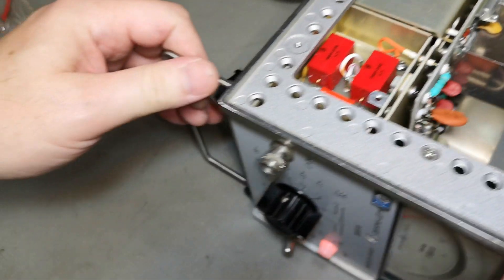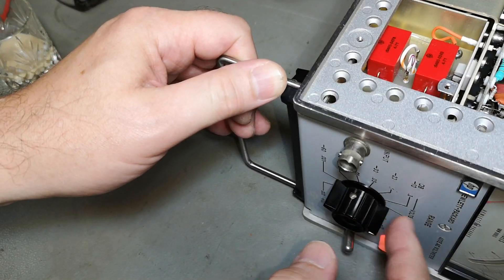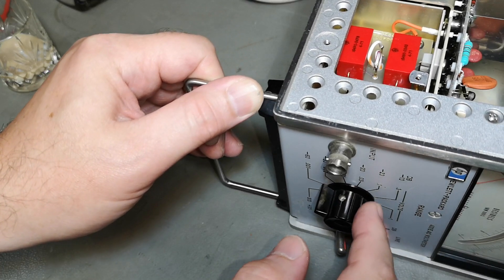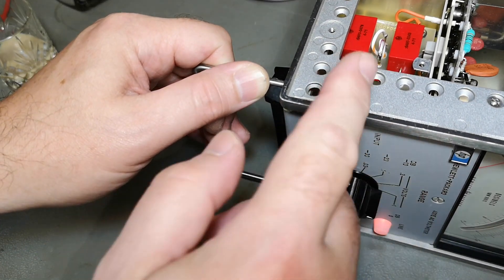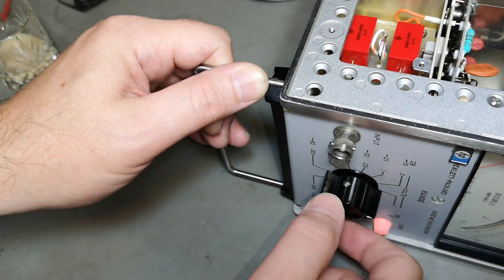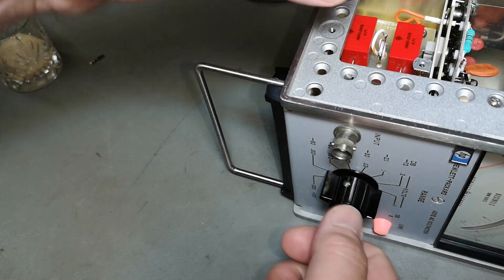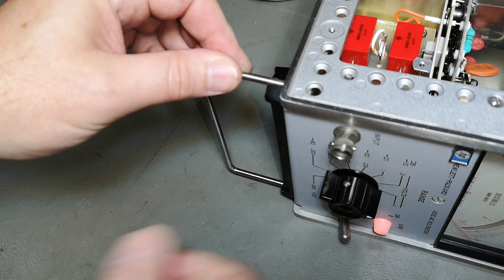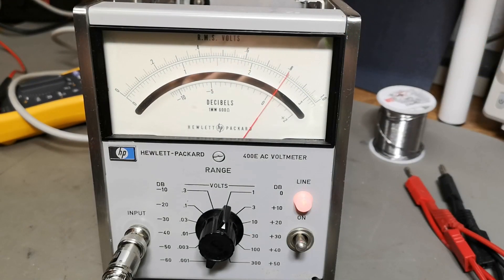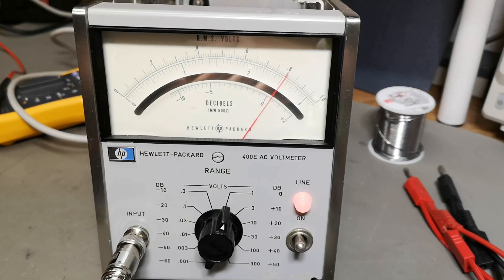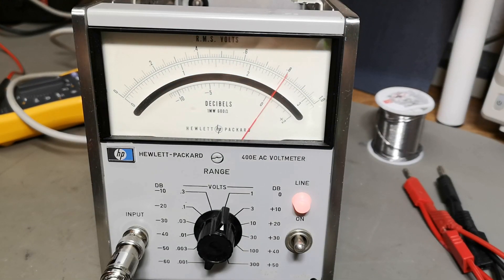I think this also explains why it happened in one range and not the other one, because it was that range where the relay was supposed to be energized and then it wasn't. So pretty good. I think I'm more or less done finally with the HP 400E.